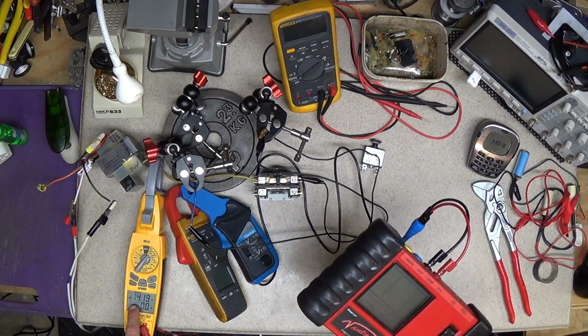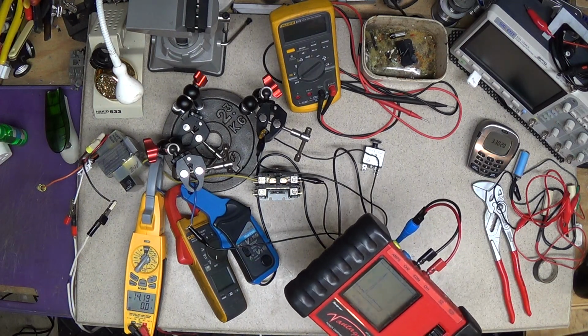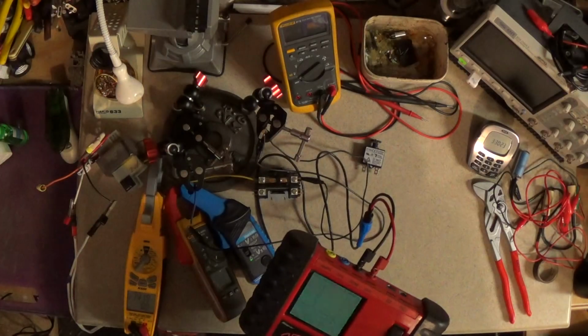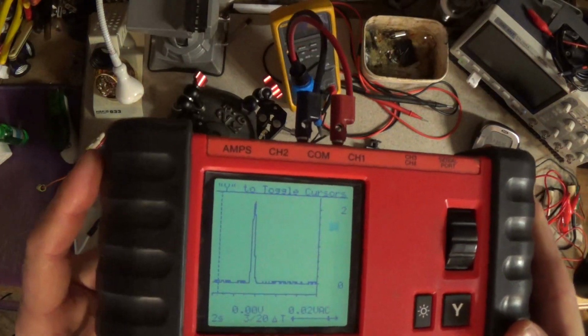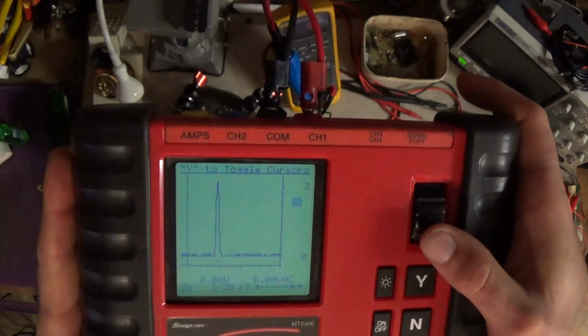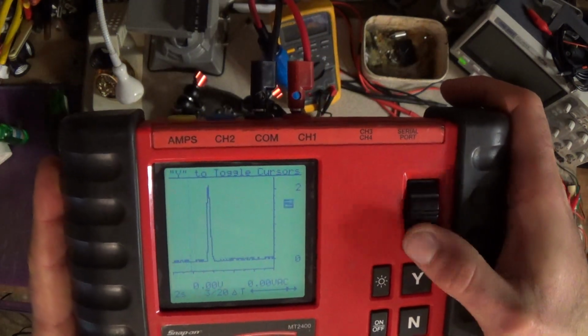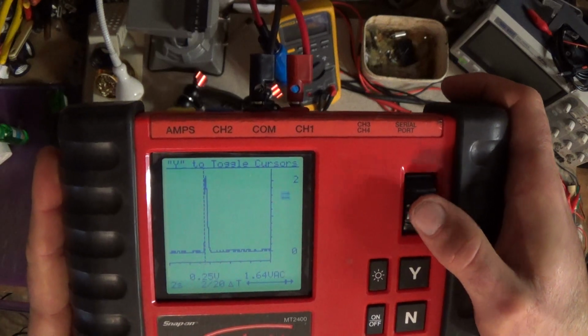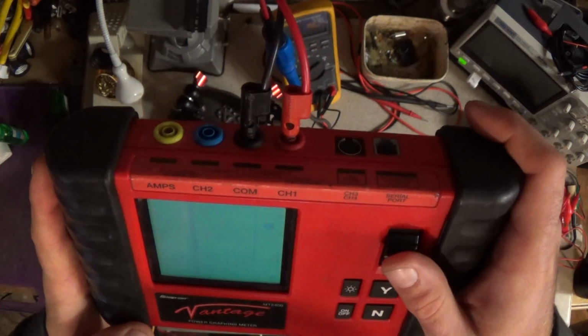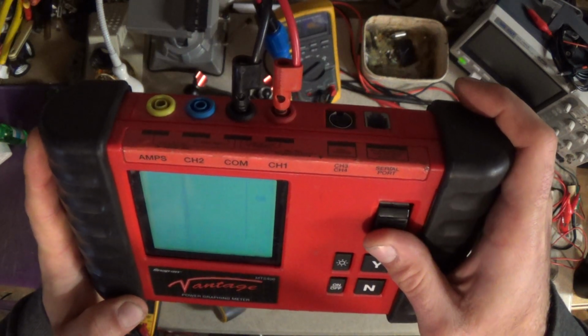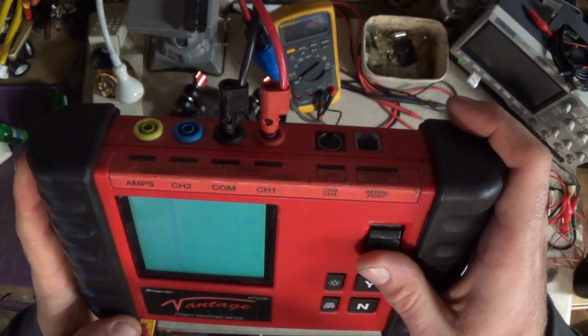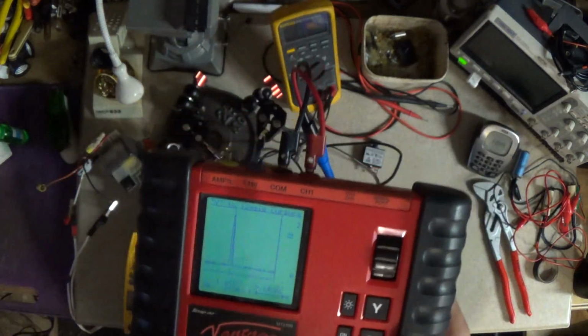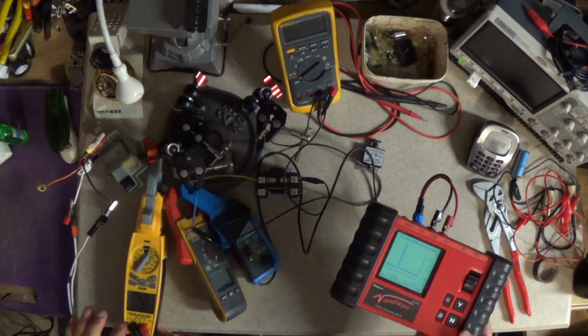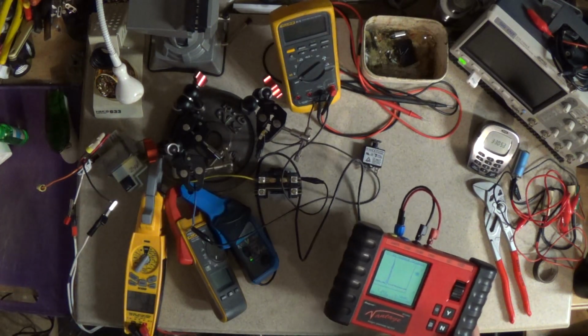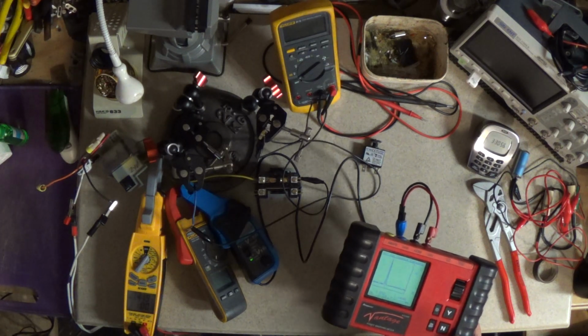Okay, so I had 14 amps inrush, and here's what the spike looked like - a shorter time base than the PTC. Obviously the PTC is going to take a little bit of time, and I had 16.4, 18.1. So again, a graphing meter, even though it's fast, doesn't always get the sample right at the exact moment because it's only taking 1 or 2 readings.